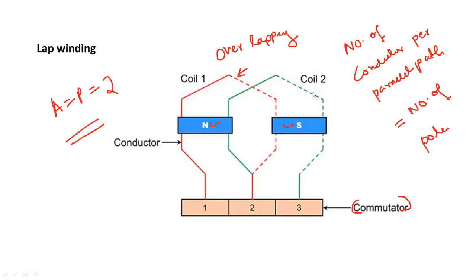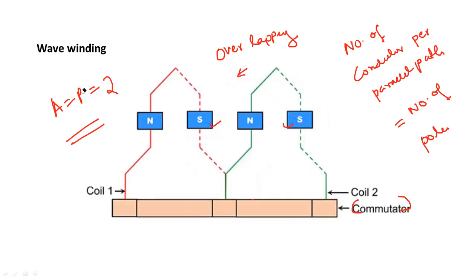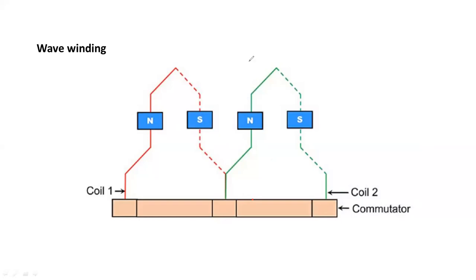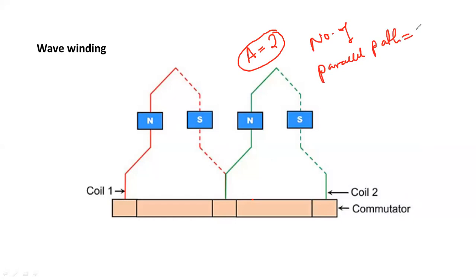Now moving on to wave winding — the second type is generally called wave winding. In case of wave winding, there is no overlapping. Always remember that in wave winding, there will always be two number of parallel paths. A is equal to two in case of wave winding. Number of parallel paths will always be equal to two only.